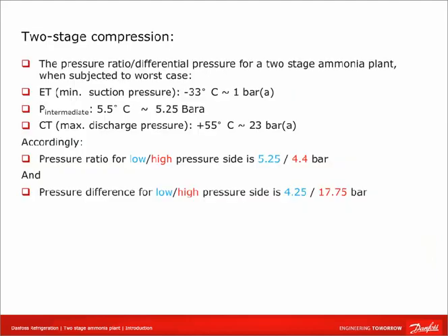Looking at the pressure ratio for a two-stage ammonia plant at worst case — -33°C at the suction side and +55°C at the discharge side — this gives a pressure ratio of 5.25 or 4.4 bar and a pressure difference of 4.25 or 17.75 bar. Based on this, we need to choose the compressor.